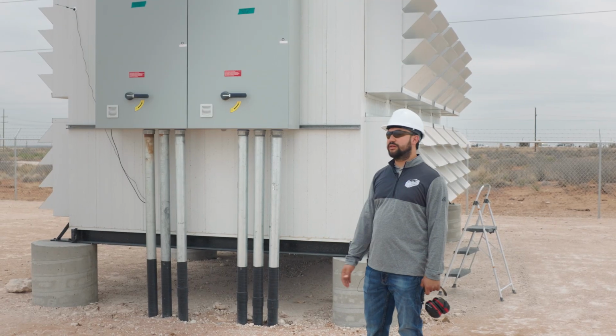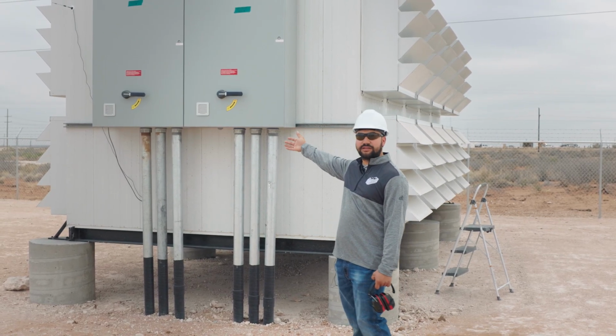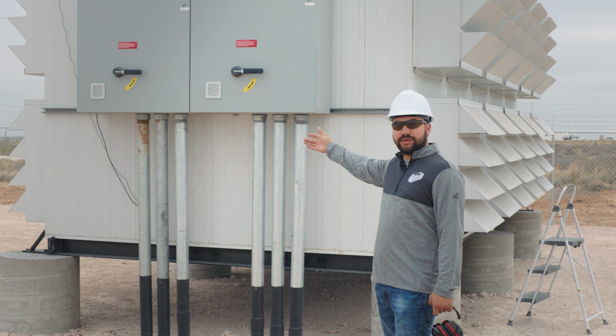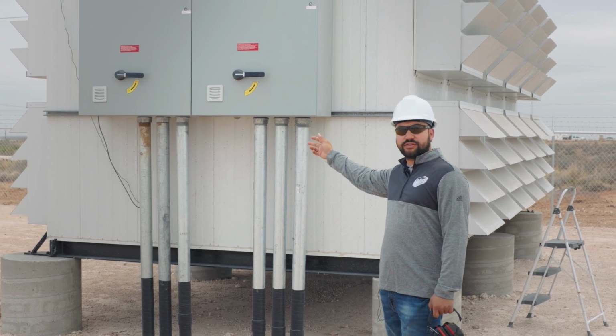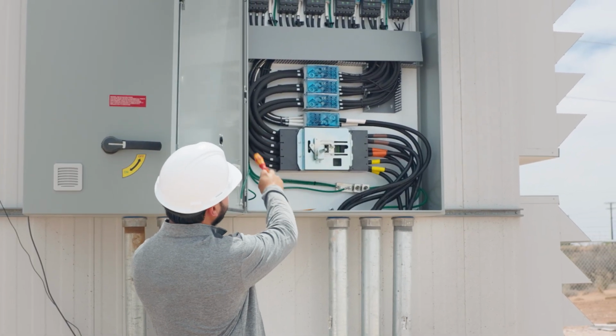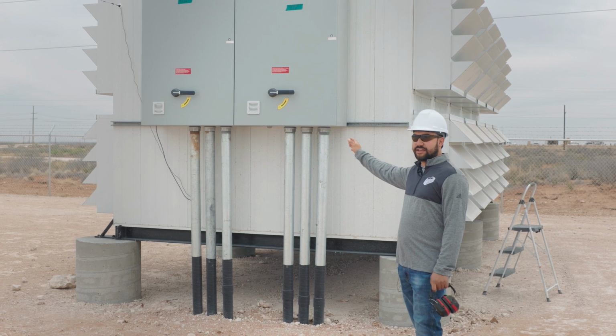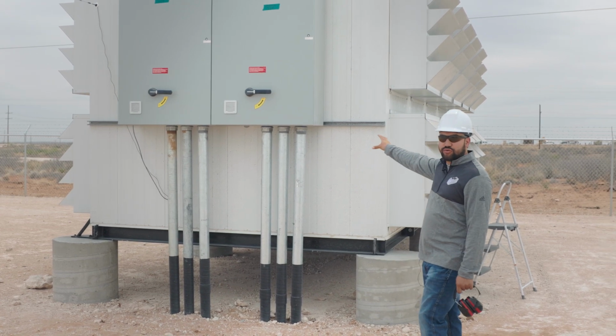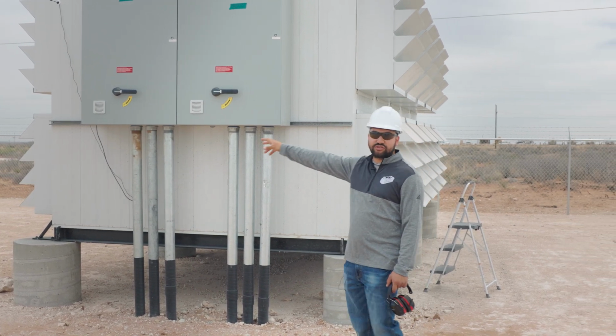From the transformer, they make their way to this cabinet, which is our main breaker panel. From here, there are two 800 amp breakers, which I call the main breakers, controlling the whole facility inside. The right side of the container is controlled by the right panel, and the left side is controlled by the left panel.